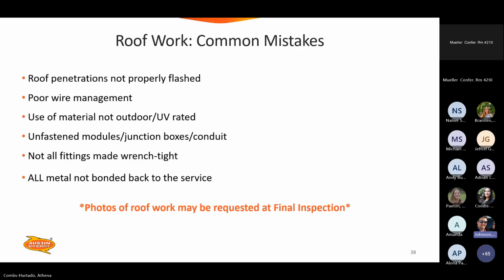All right. Roof common mistakes. Roof penetration is not properly flashed. When we penetrate through the roof, we have to have what's called a witch's hat or a boot that actually re-weatherizes and insulates the building envelope. Poor wire management. I saw one yesterday that looked like a bowl of spaghetti on the roof. The wires need to be up off the roof per NEC, 3/4 of an inch, just to where nothing is touching the rooftop. Use of material not outdoor or UV rated.